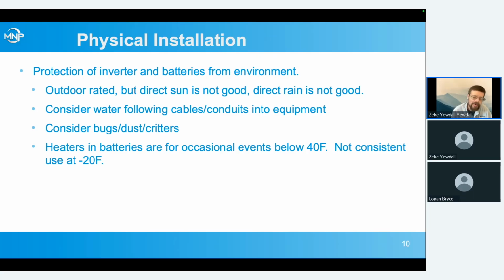The PowerFlow 5 batteries, the rack mounts, those are not supposed to be mounted outdoors. In a garage or something, that's fine, in an equipment building, but you can't just stack them up outside. Some of the new cabinets we're working on, or if you have a NEMA 3R rated cabinet, they could go outdoors, but generally they're not something we would put outdoors.